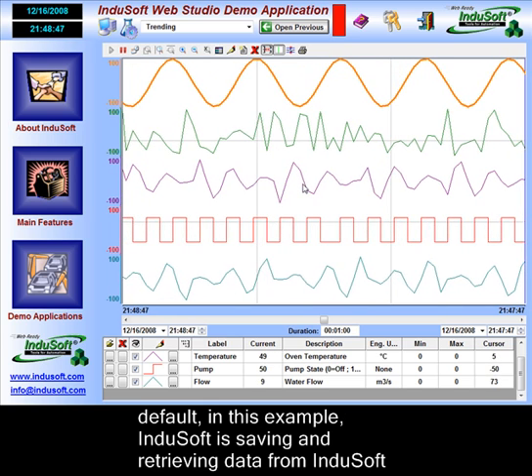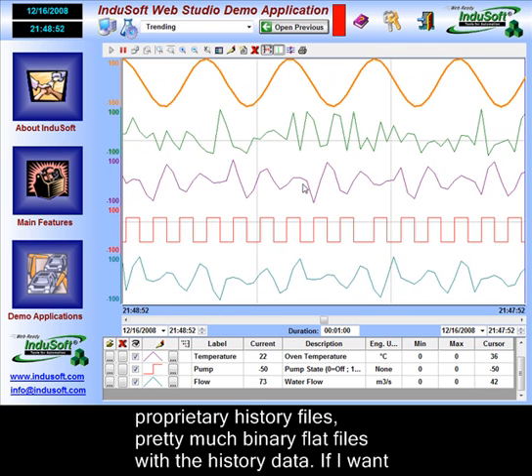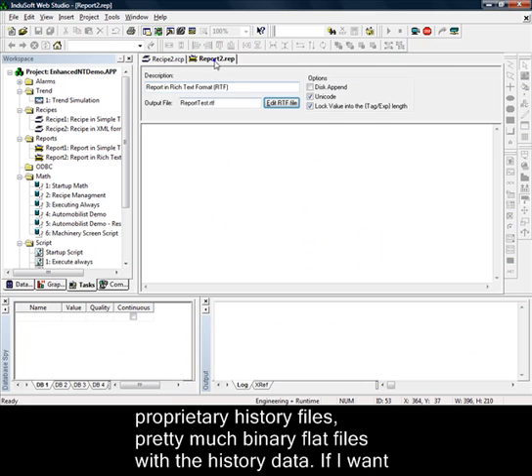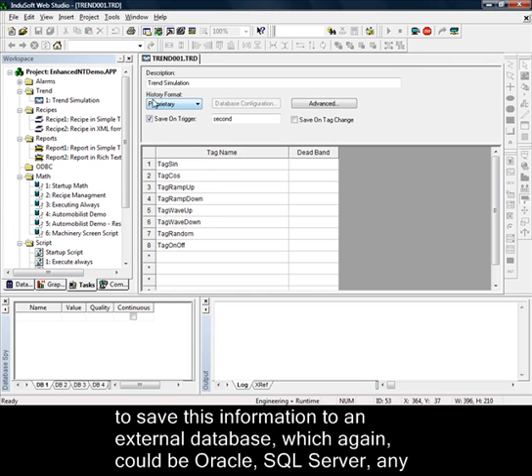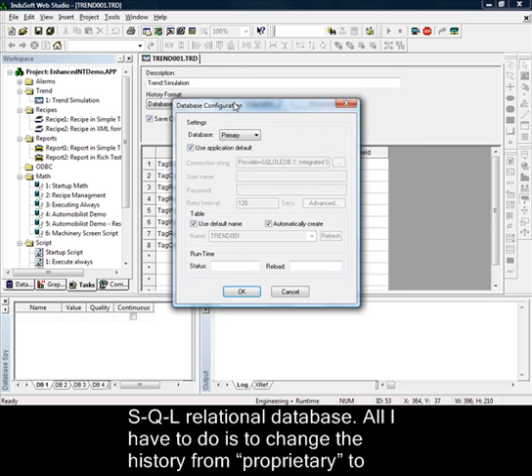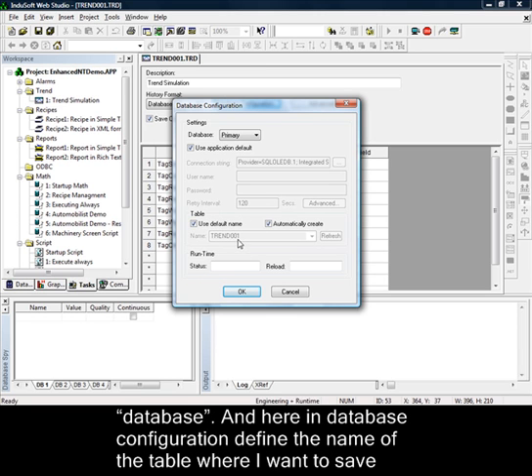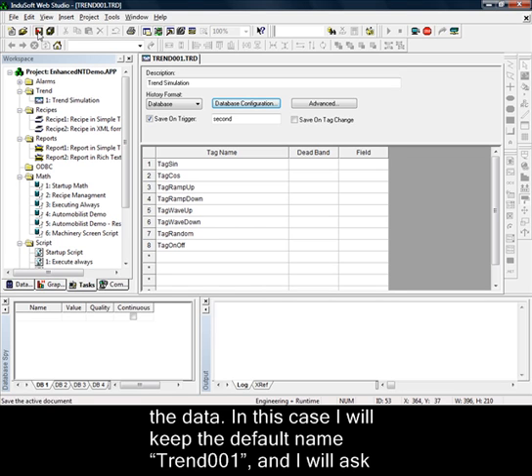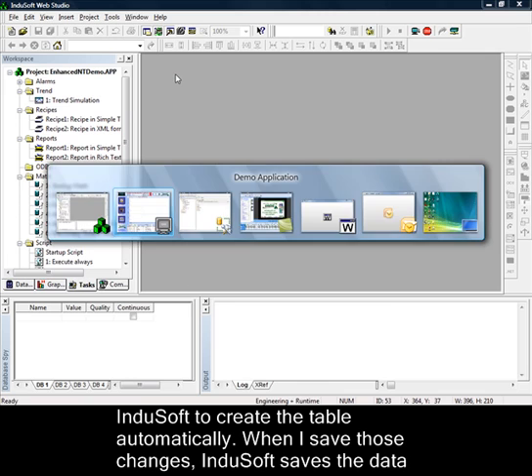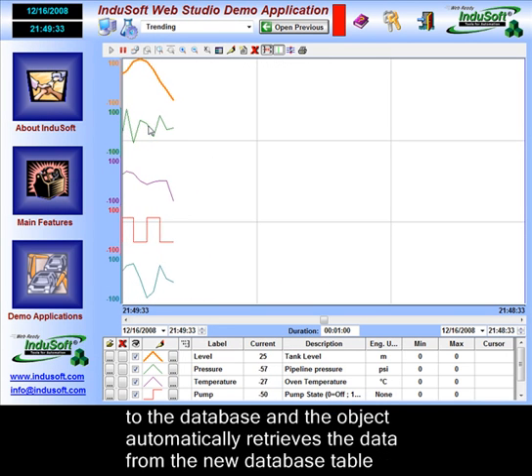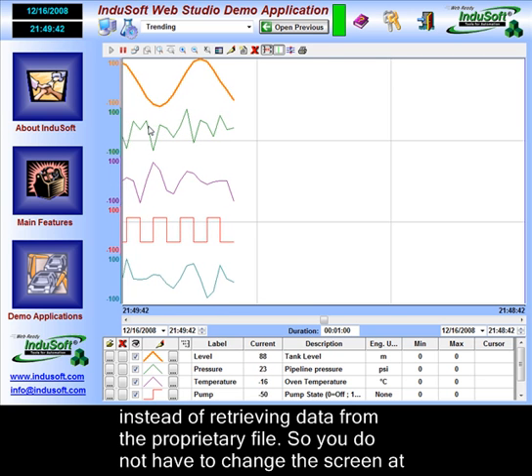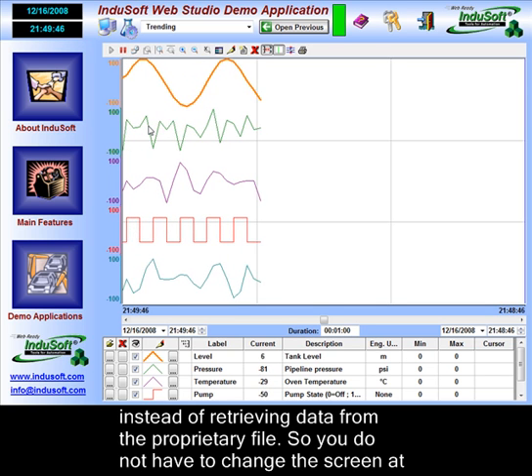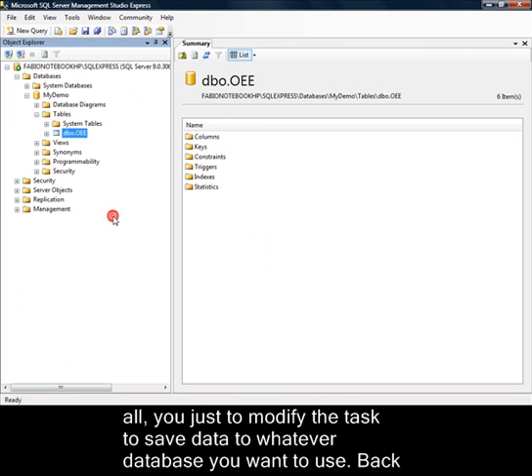By default in this example, Indusoft is saving and retrieving data from proprietary history files — essentially binary flat files with the history data. If I want to save this information to an external database — which could be Oracle, SQL Server, or any SQL relational database — all I have to do is change the history from proprietary to database, and in the database configuration define the name of the table where I want to save the data. I'll keep the default name trend001 and ask Indusoft to create the table automatically. When I save those changes, Indusoft saves the data to the new database, and the object automatically retrieves data from the new database instead of the proprietary file — without changing the screen at all.